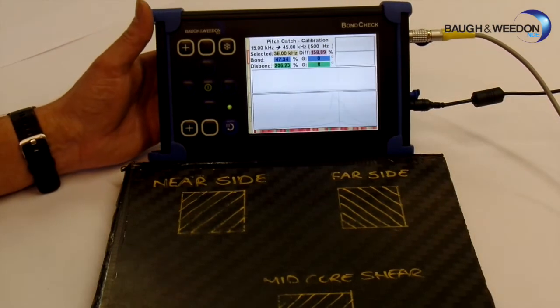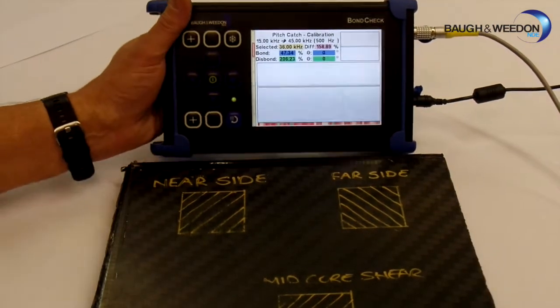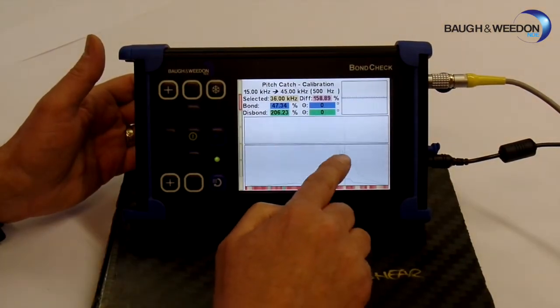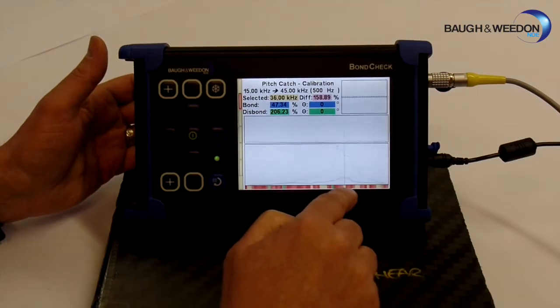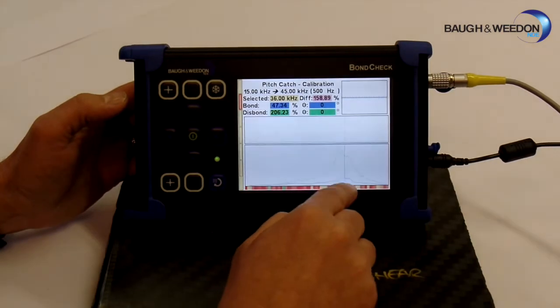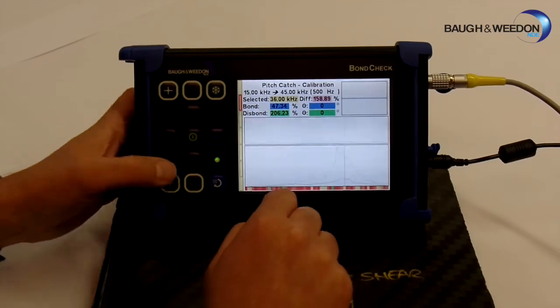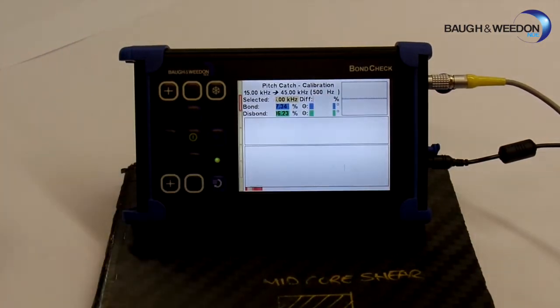So that is the actual calibration finished as such. But what it has done there is, I will just bring it closer, what it has done is it has picked the frequency where the largest amplitude difference is, and also the quality. It looks at a quality signal as well. Now the system has picked this one as its best option, so what we are going to do is select that.